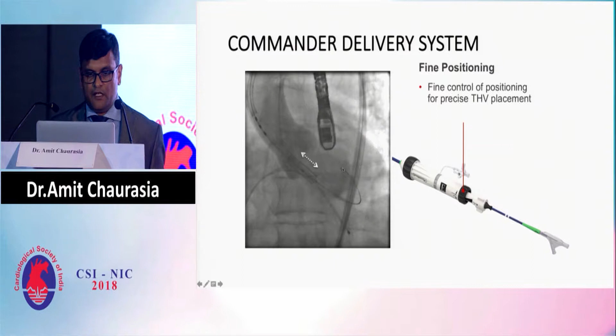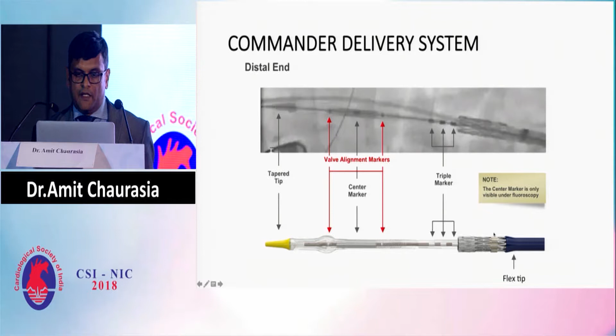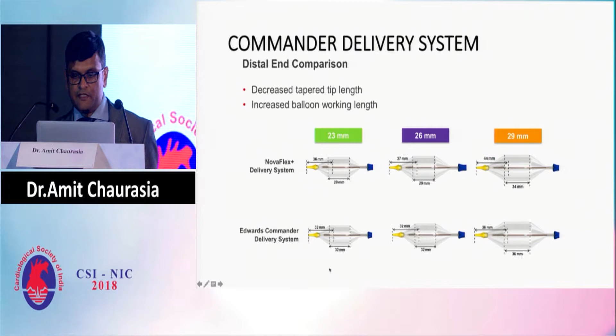Now the system has a taper tip. This helps to decrease the profile while you enter into the sheath and into the aorta. The balloon actually has a triple marker. The central marker, you cannot see outside. You can only see it under fluoroscopy. And then there is the valve that has to be loaded over the flex sheath and all. The Commander delivery system actually comes with the balloon, which is different for different sizes of valve, 23 millimeter, 26 millimeter, or 29 millimeter, and the length of the balloon differs accordingly.